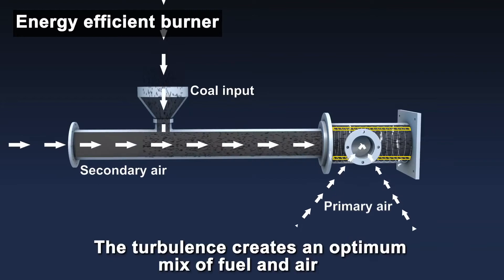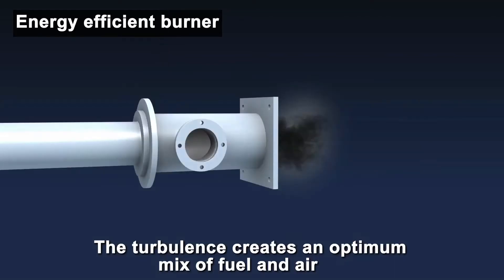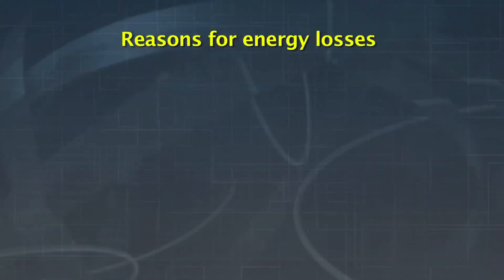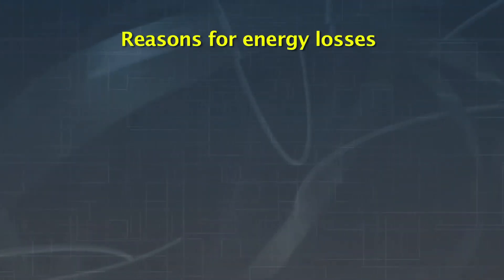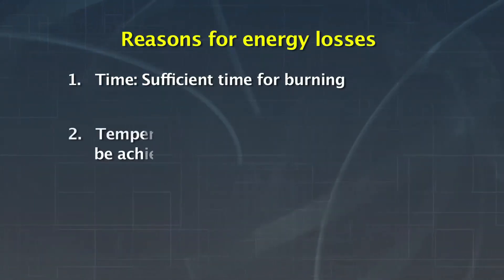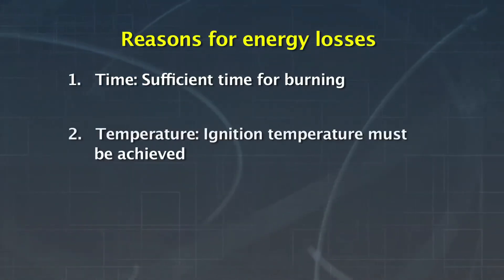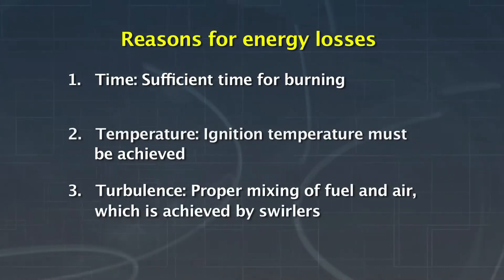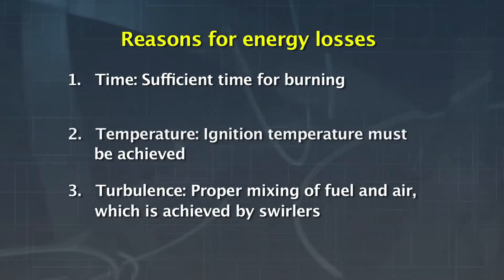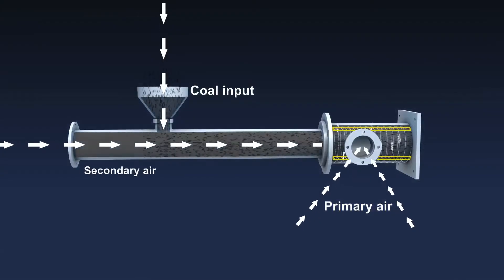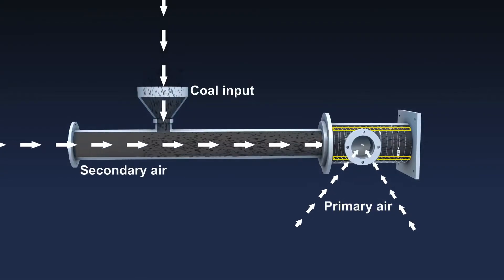The hot secondary air is also utilized for the complete combustion of powdered coal. This burner works on the basis of the three T's of combustion: Time — sufficient time for burning; Temperature — ignition temperature must be achieved; and Turbulence — proper mixing of fuel and air, which is achieved by swirlers. Vanes are fabricated in between the annular pipes.